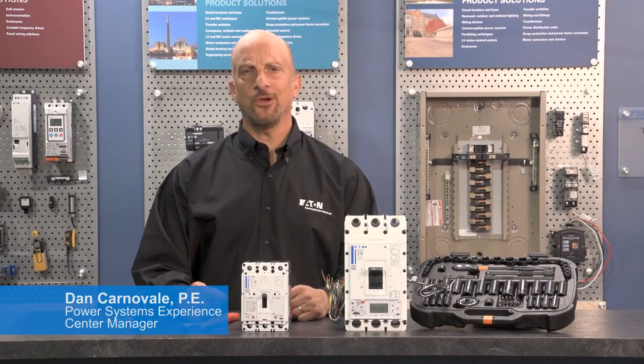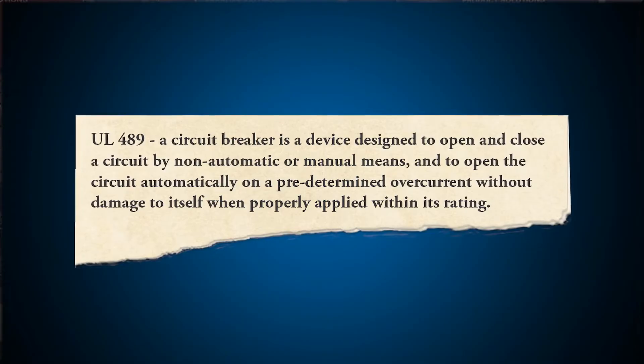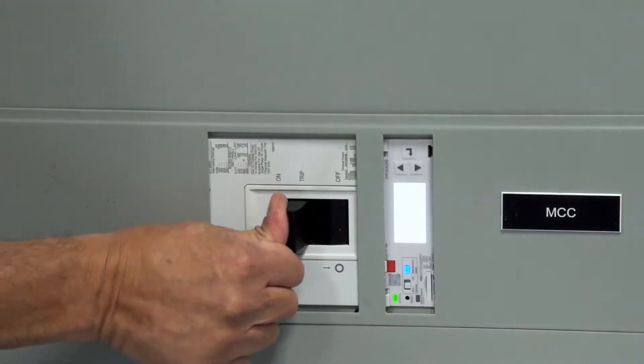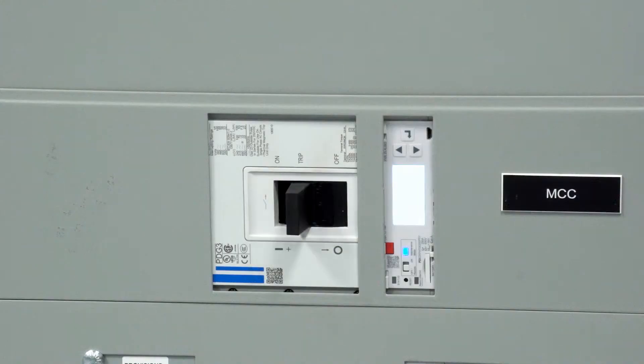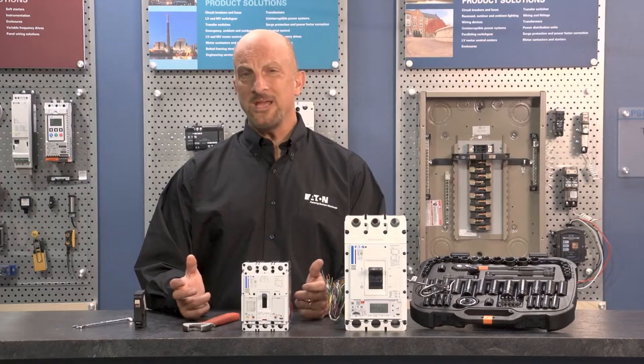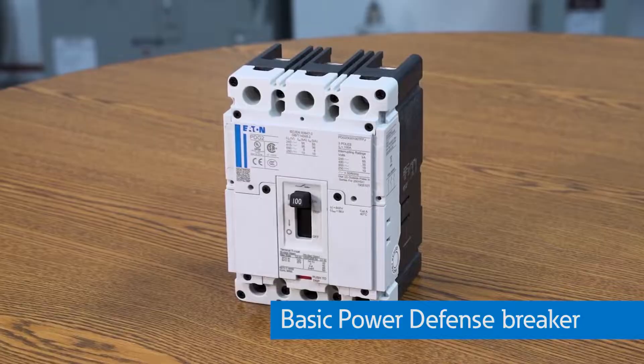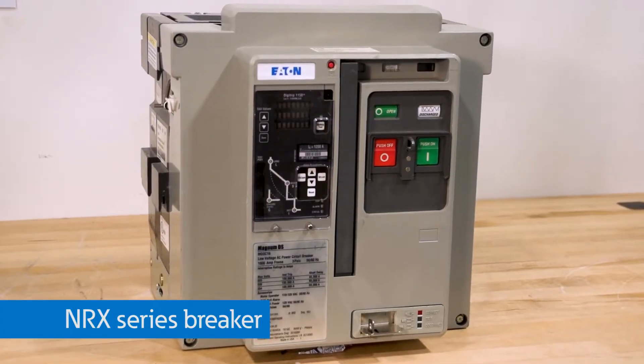Yeah, we're going to start with the basics but definitely talk about the Power Defense. So what is a circuit breaker and where are they typically applied on electrical power systems? UL 489 defines a circuit breaker as a device designed to open and close a circuit by non-automatic or manual means, and to open the circuit automatically on a predetermined overcurrent without damage to itself when properly applied within its rating. They provide feeder and branch circuit protection for wiring and are designed for overcurrent protection for overload and short circuit conditions. Basically you can categorize circuit breakers as either thermal magnetic — designed to trip on their own during overcurrent conditions — or circuit breakers that trip when another device like a relay or trip unit tells them to trip.